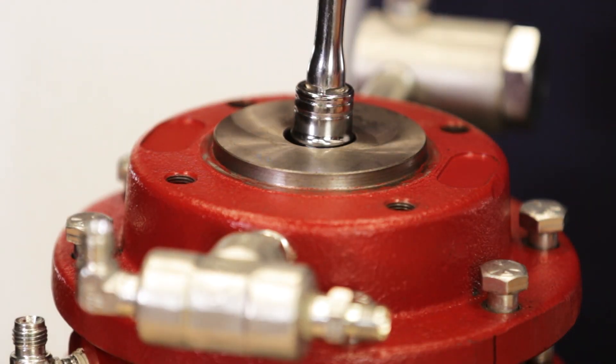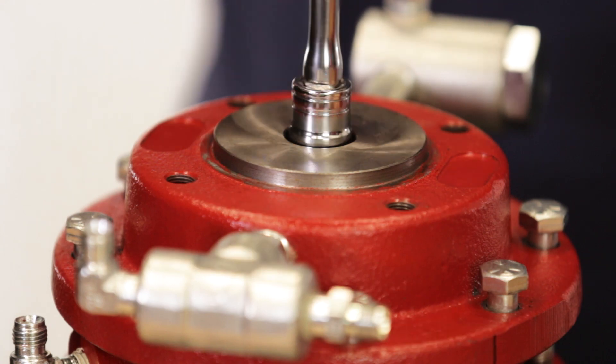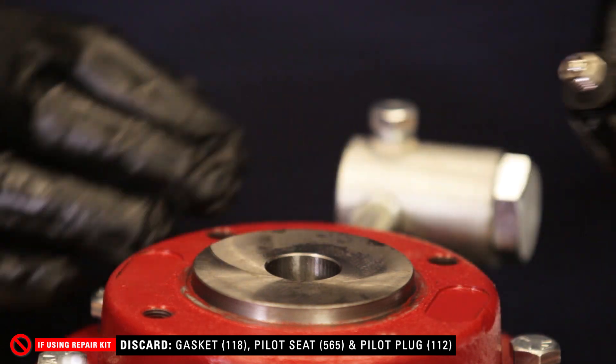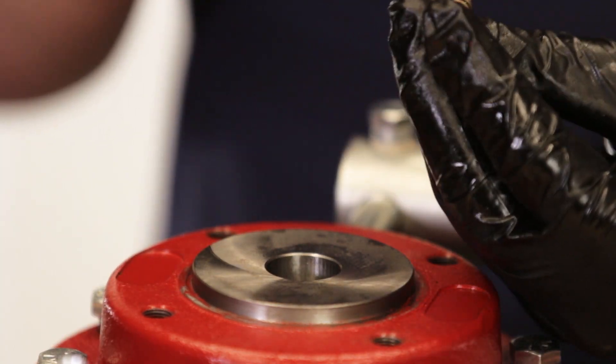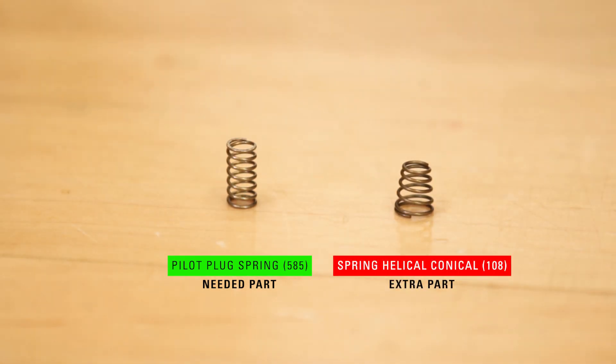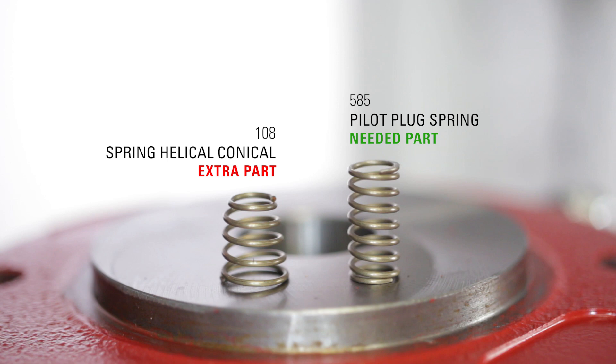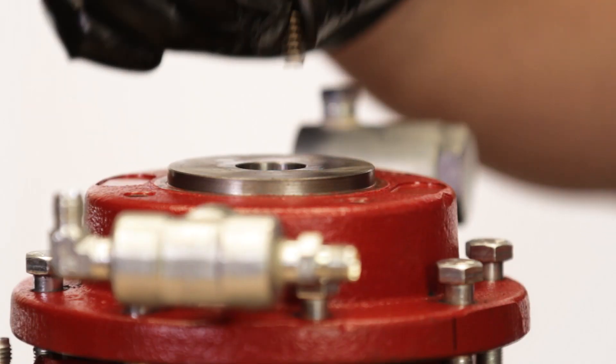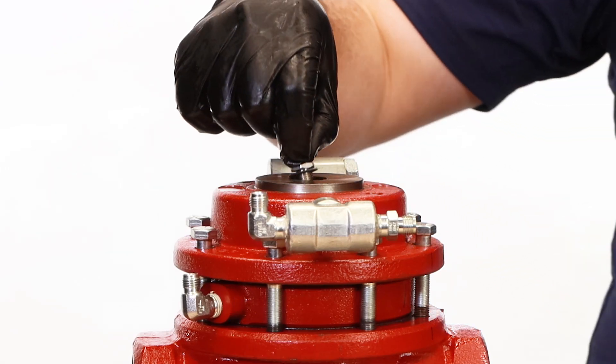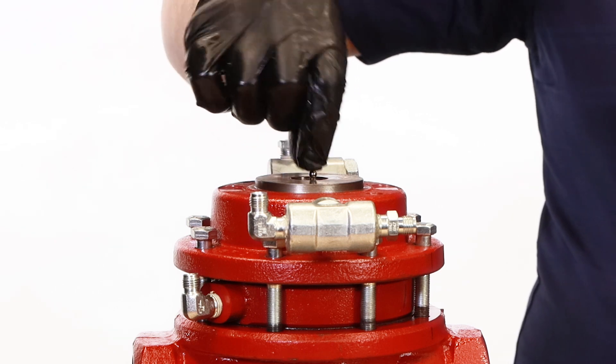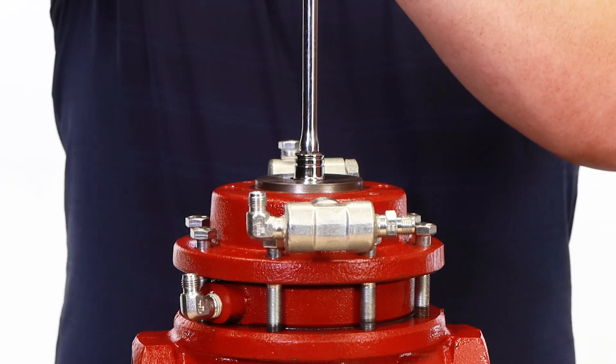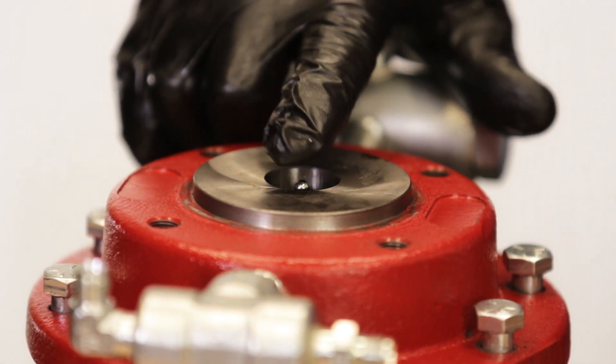Use a 9/16ths socket to remove the pilot seat. Inspect the gasket for damage. Use a pick to remove the pilot spring and set it aside. This will also be an extra piece. Put in the new pilot plug spring. Hold the pilot plug assembly by the ball of the pilot plug to keep it together while you thread on the assembly by hand. Then fully tighten it with a socket wrench. Verify that the pilot plug can move freely before continuing.